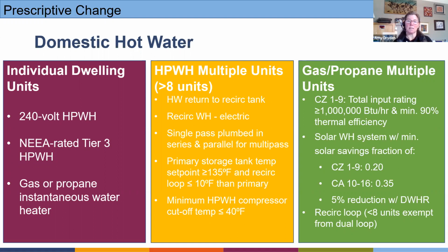If we're looking at central heat pump water heater systems that are serving multiple units, and we're saying this is greater than 8 units, there are some additional prescriptive conditions that are required. And really this is to get at what we can put into place to support the higher performance of that central system. For those of you who have been involved in modeling or installing or working within the code on central heat pump water heater systems, it's definitely been an evolving process in terms of what is included in our software and what's allowed.